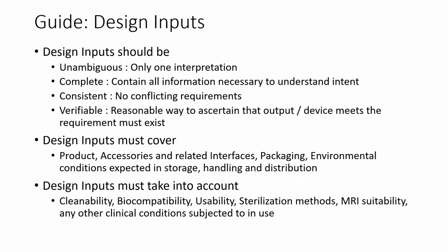A design input should be written in such a way that a particular statement contains only one input. So you should not be mixing requirements for two different parameters into a single statement. So that's what it means when it says unambiguous. There should be only one possible interpretation. There should be only one particular need that is defined in one input. The statement should be complete by itself.